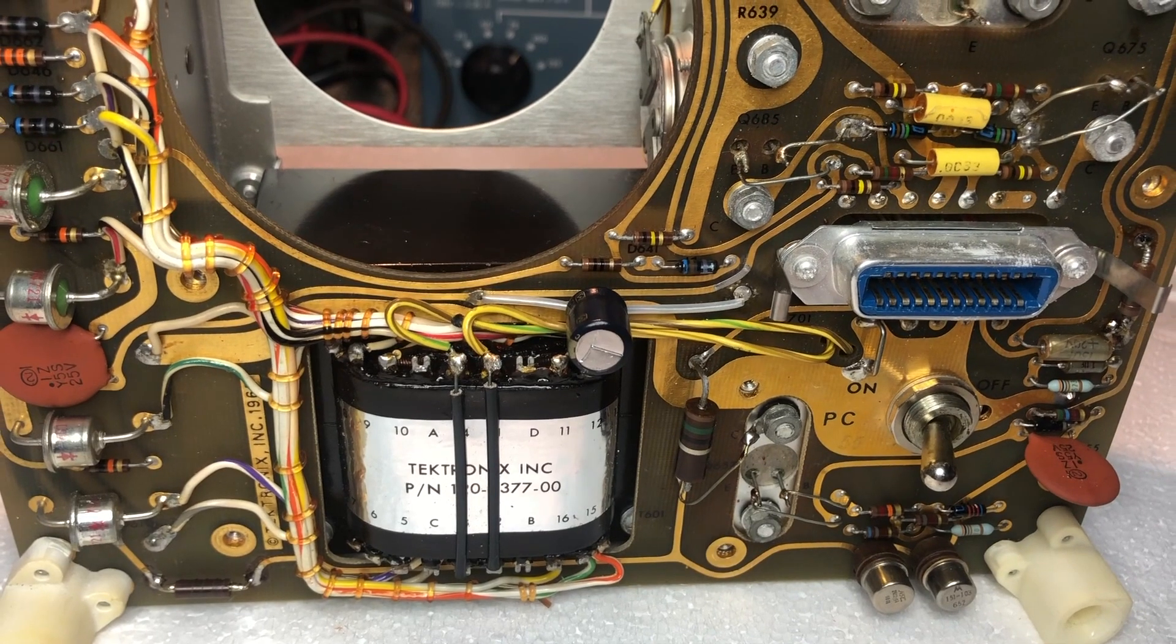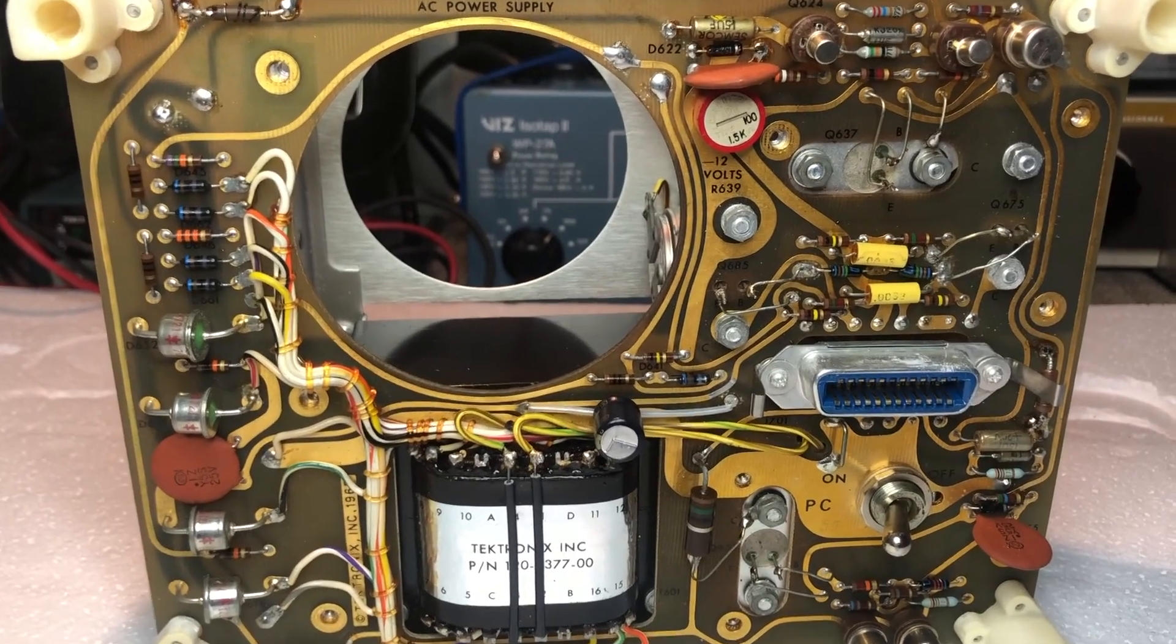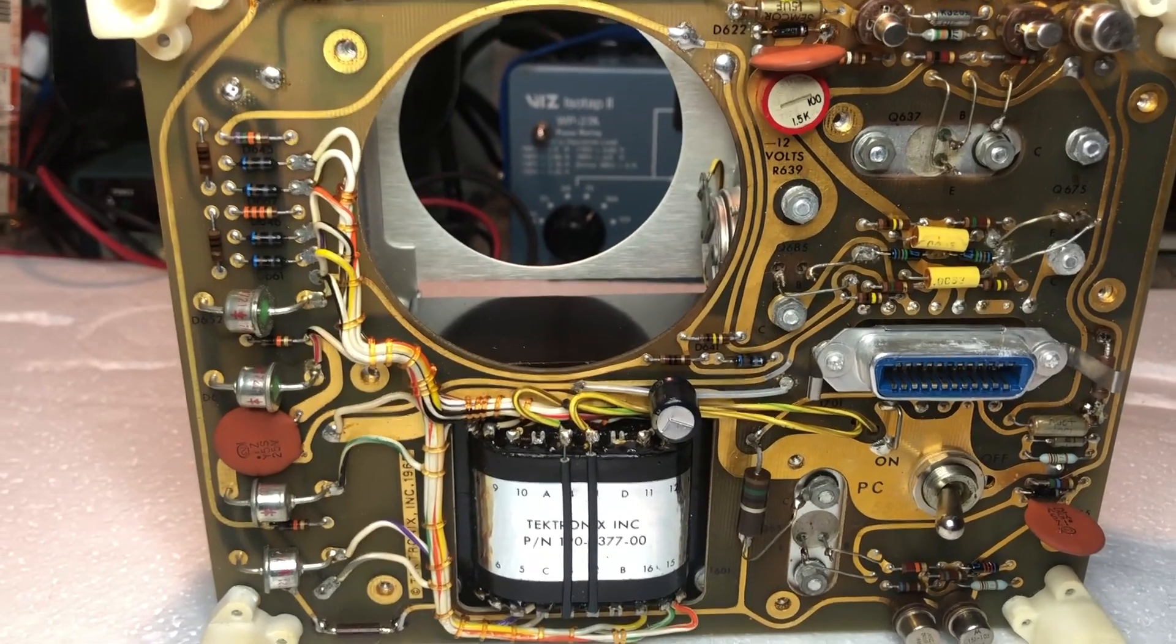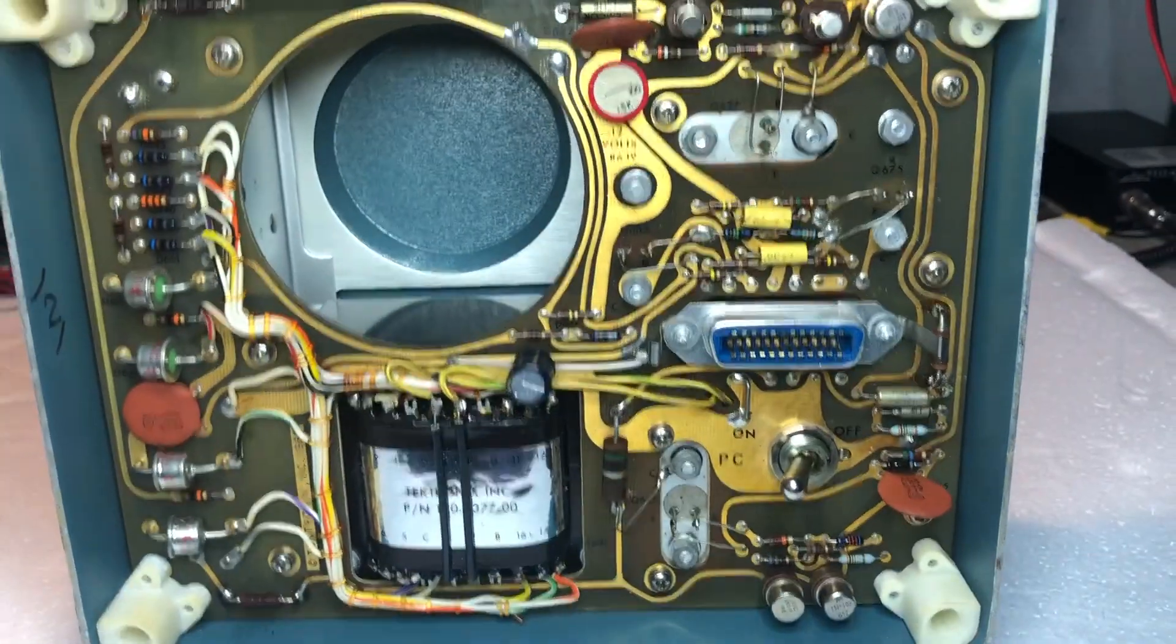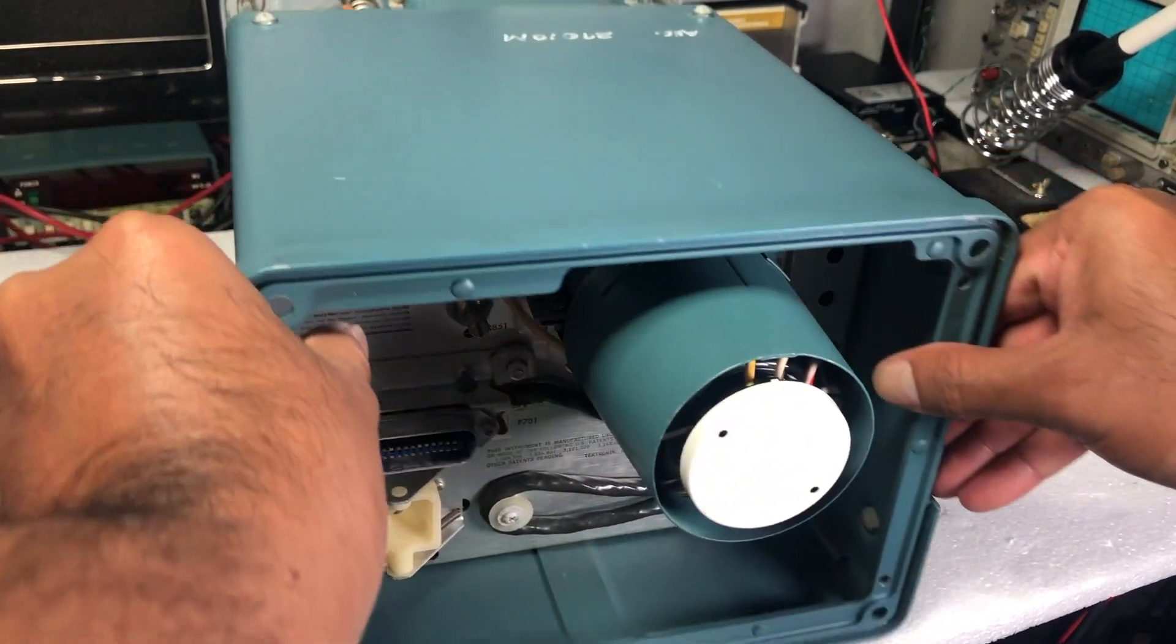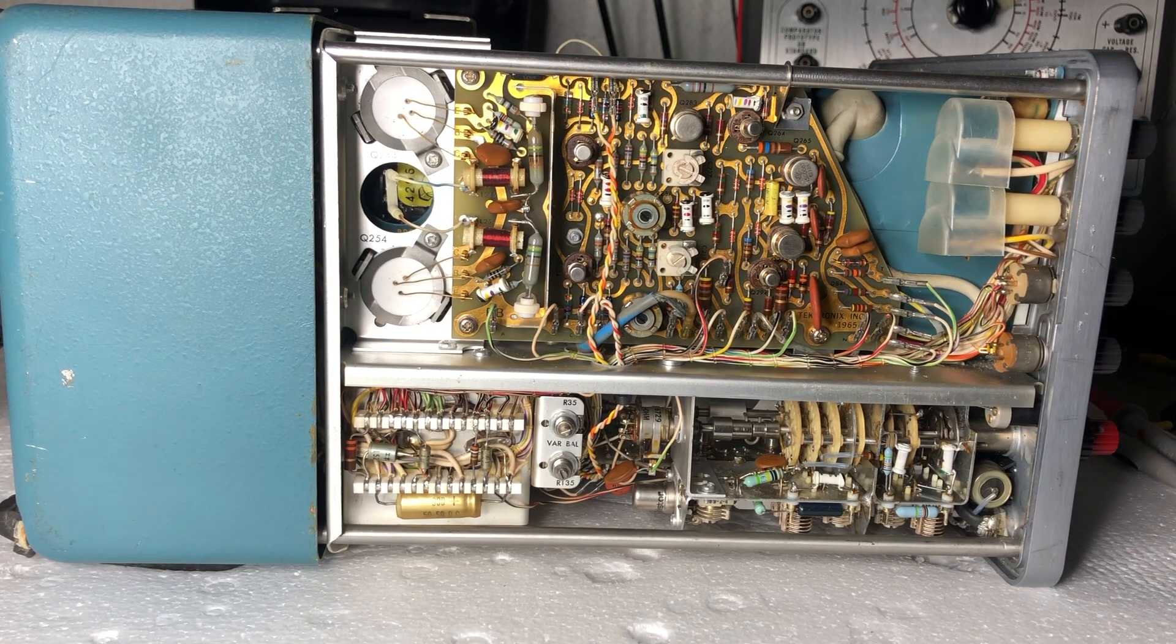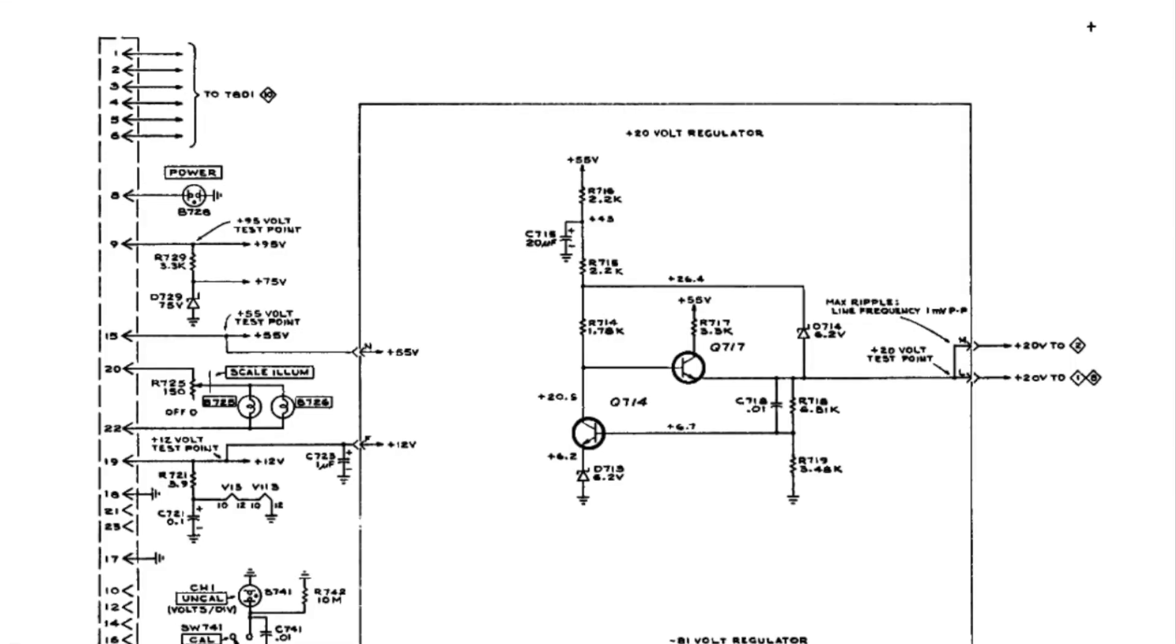This power supply checks out good. I'm going to put it back into its case, then we will hook it to the indicator unit and start troubleshooting it. One key thing is, even though this is called a power supply, this doesn't have all the regulators. The rest of the regulators are inside the indicator unit. Okay, I'll put it back together now. Let's get to the indicator unit. There are three screws holding the cover. Once you remove that, you can slide the indicator unit cover out. I've assembled the indicator unit and power supply unit together. Now let's test the voltages from the indicator unit because there is one more set of regulators inside the indicator unit.